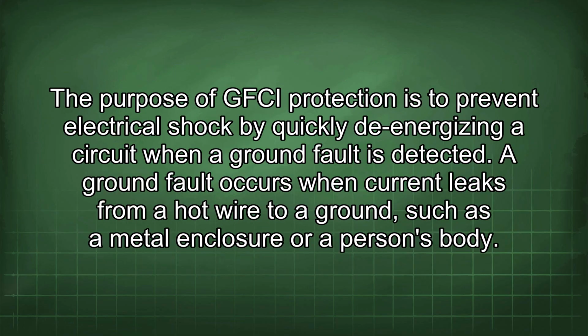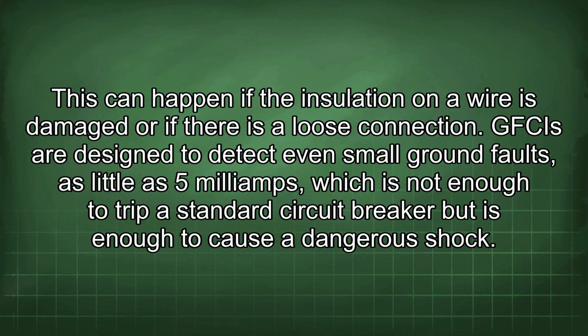The purpose of GFCI protection is to prevent electrical shock by quickly de-energizing a circuit when a ground fault is detected. A ground fault occurs when current leaks from a hot wire to a ground, such as a metal enclosure or a person's body. This can happen if the insulation on a wire is damaged or if there is a loose connection. GFCIs are designed to detect even small ground faults, as little as 5 mA, which is not enough to trip a standard circuit breaker but is enough to cause a dangerous shock.